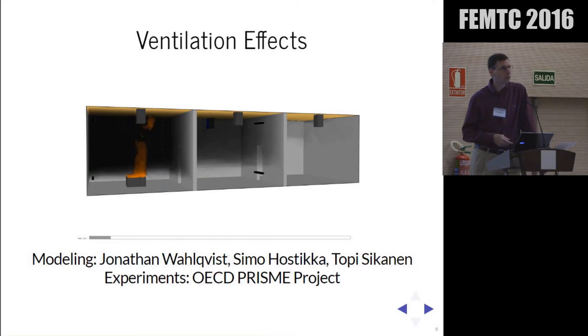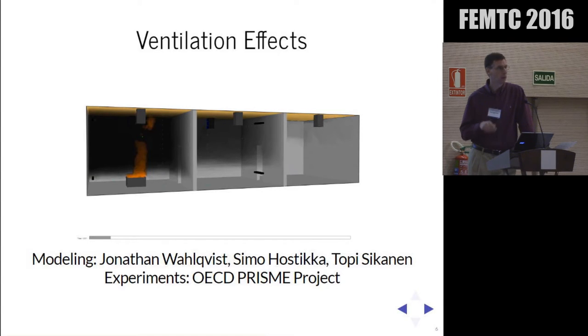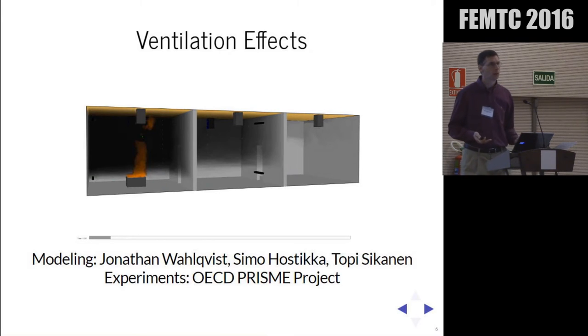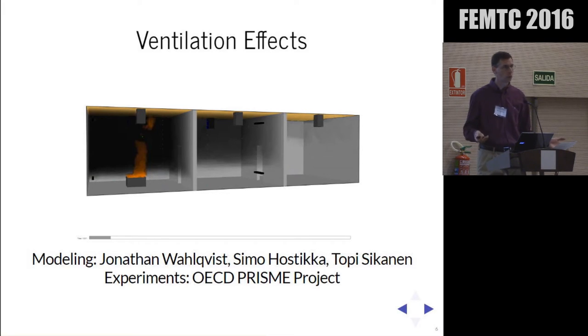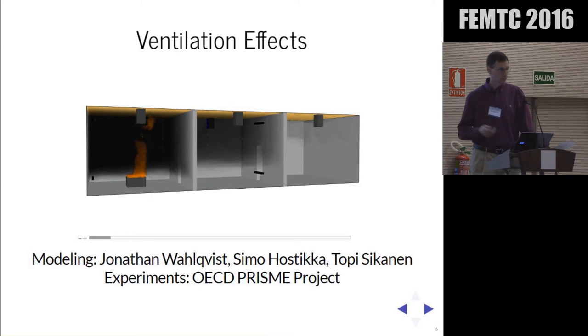Here's other work donated to us by Simo Hostikka, Topi Sikanen, and Jonathan Wahlqvist, who was at Lund. The PRISME experiments were done in France by the nuclear authorities to look at fires within nuclear power plants — fairly straightforward experiments done in a facility with an elaborate ventilation system. We did not have anything in our guide to demonstrate that the ventilation routines in FDS actually work. We had verification work but no validation work. So they put together these experiments and we put them into our guide.